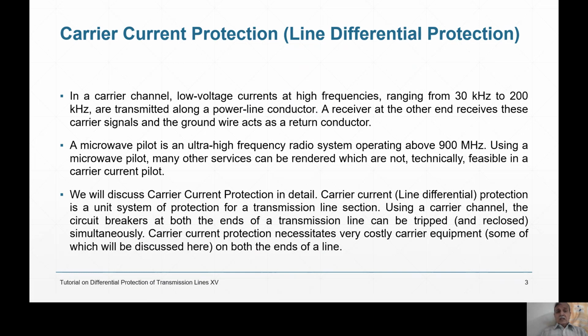So what we do is, normal power frequency current at very heavy megawatt, 200 megawatt or 300 megawatt, is flowing. But our carrier signal is at very low wattage, at very high frequency, in the range of 30 to 200 kilohertz, and it will flow to carry many pieces of information. The transmitter will transmit the information at high frequency, the receiver at the other end will receive it, and it will do the function. That is a carrier channel.